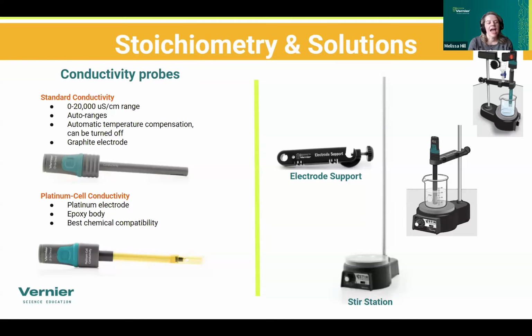So it really has a lot of advantages that I'm a big fan of in the conductivity probe. However, the standard one has a graphite electrode, so you will get polarization effects over time. We've done a lot of things to mitigate that in how we've set up the circuitry inside, but that will happen. And then also the plastic that the shaft of the conductivity electrode is made out of is ABS plastic. So if you're doing measurements in ethyl acetate or anything that's non-aqueous, strong acids and bases, you are going to erode that plastic over time, and you might have to replace it eventually.